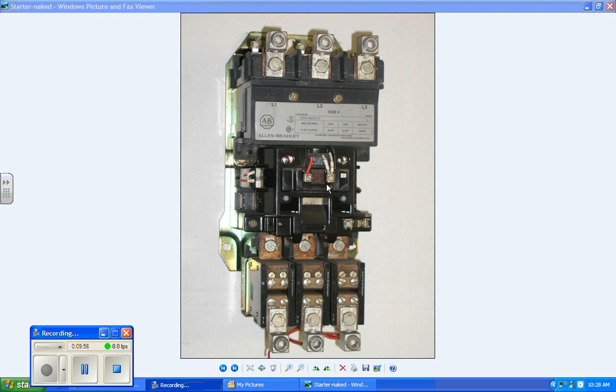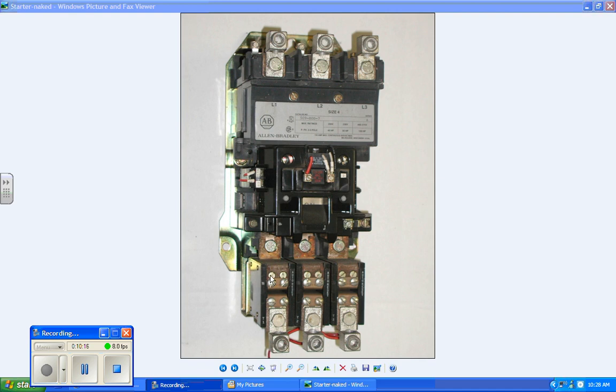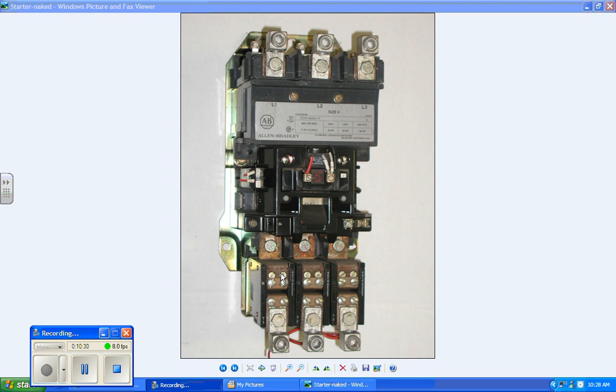Now having started talking about overloads, once again we want to go back to page 37. That lower bottom half of the page is what's called a solder pot overload. The ones you're looking at in this diagram right here are solder pot overloads, and they can be reset once they cool off. They have to cool off before you can reset them. There are bimetallic strips that will work the same way more or less, and again they can be physically reloaded so that you can reset them.